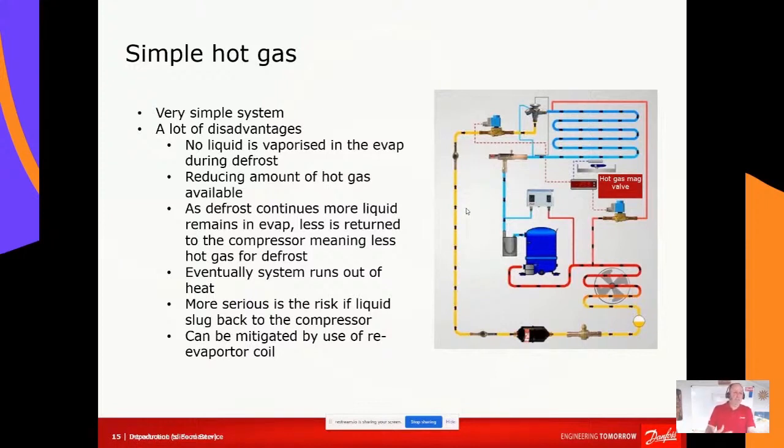So yes, it can work, but if you ask me would I install it, then not really, because it would run out of hot gas. For a proper hot gas system, you need at least in a medium temperature system at least two evaporators running and one on defrost. And then if it's a low temperature application, you need at least three evaporators running and one evaporator on a defrost to actually generate the amount of hot gas required to melt that evaporator.